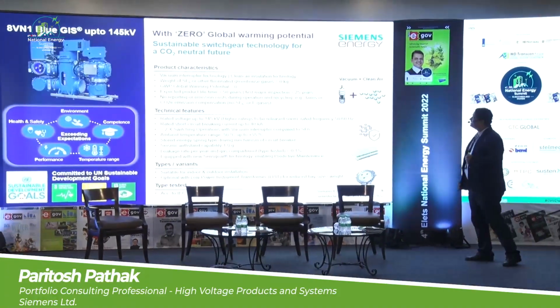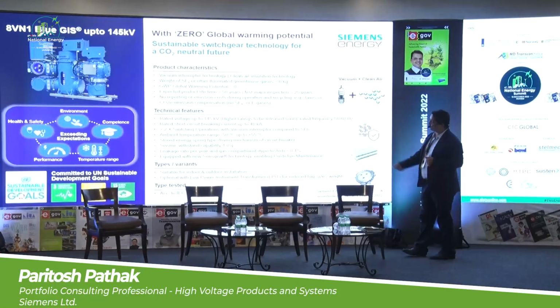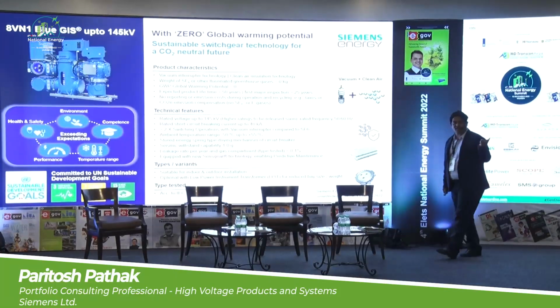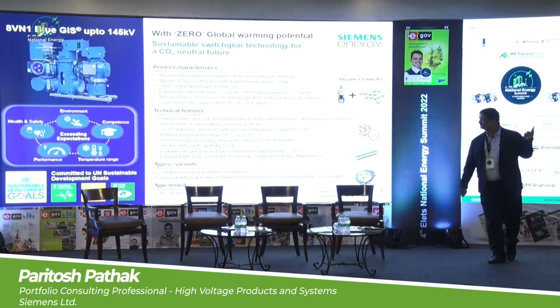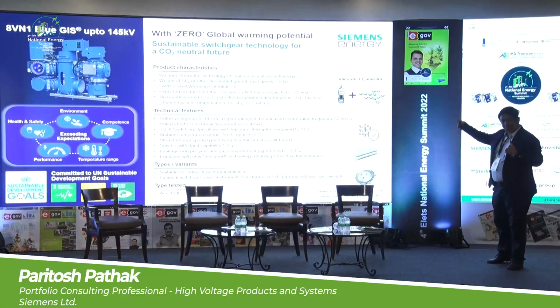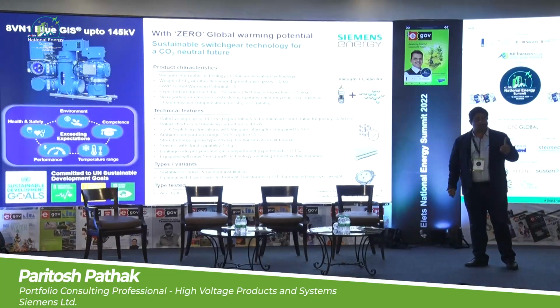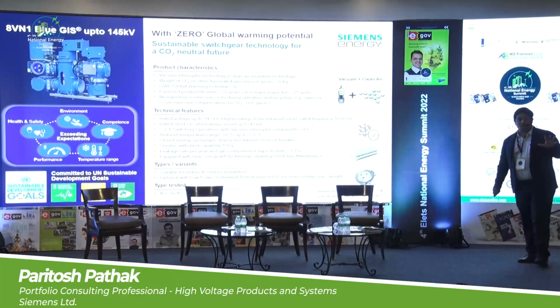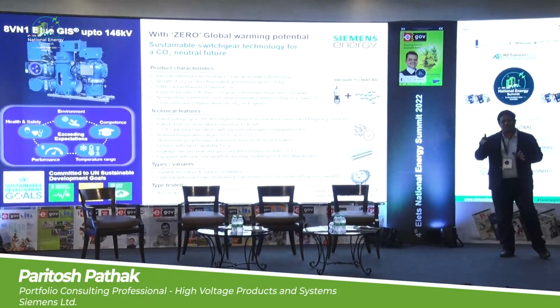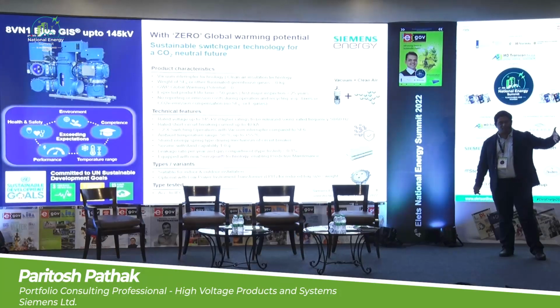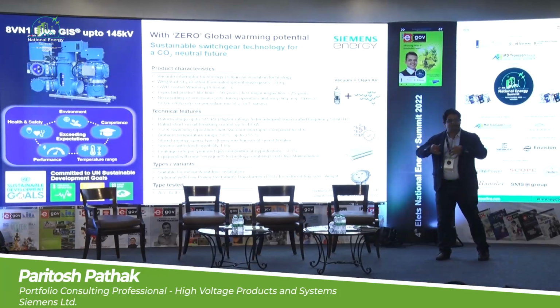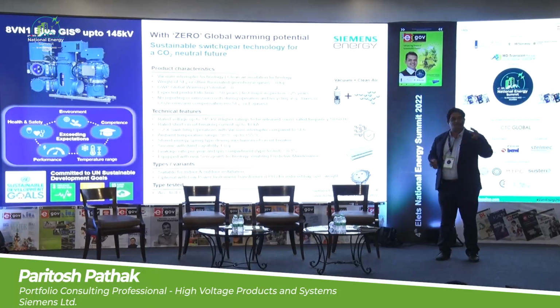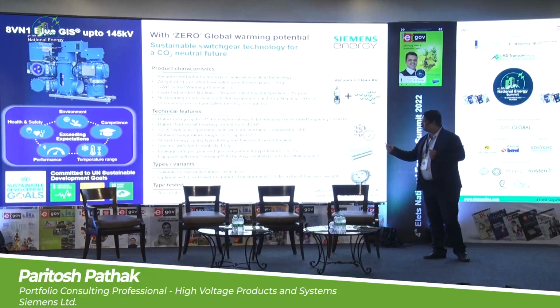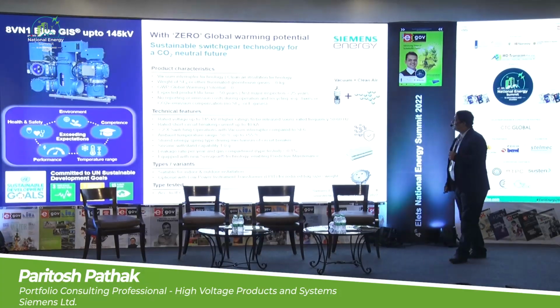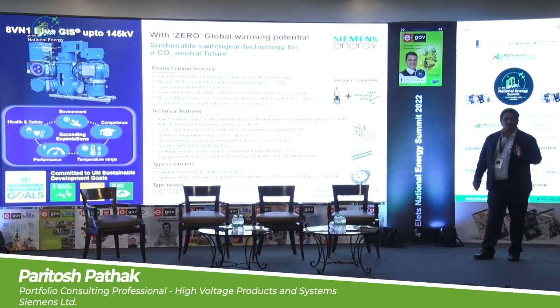Sustainable switchgear technology for a CO2 neutral future — what are the product characteristics? As mentioned, clean air and interrupter technology with vacuum. Weight of SF6 or other fluorinated gases is zero, global warming potential is zero. Expected product lifetime: we know SF6 gas insulated switchgear had a life expectancy of more than 50 years — this is the same, a completely sealed environment, gas insulated switchgear with clean air, with no reporting or emission cost during operation and recycling, and no taxes or CO2 emission compensations required. This is a foolproof technology, available and implemented.